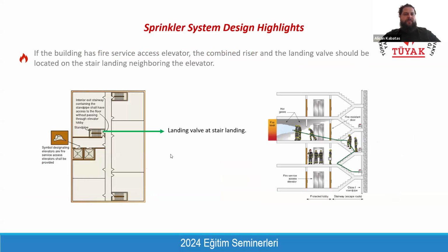And also, if your building has a fire service access elevator, we recommend providing this riser and landing valve in the stair which is neighboring the service access elevator, because as you can remember from the last lessons that we held together, the fire brigade comes up to one floor below the fire incident, and they prepare there, and they use the landing valve, and they go into the fire incident floor. That's why it is very important that they have a landing valve within the stair.